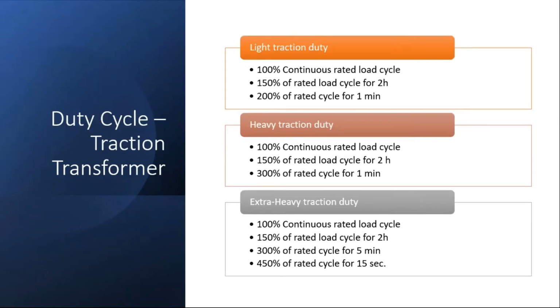The duty cycle requirement for the traction transformer is covered in this slide. So what happens if the customer specifies just light traction duty? The standard requires that it has to operate continuously at 100% load and at 150% load for 2 hours, and then occasionally at 200% for a minute. So this is the requirement as per the standard. When we operate at 150% or 200%, the limit as per C57.18.10 is 140 degree hot spot temperature for liquid type.